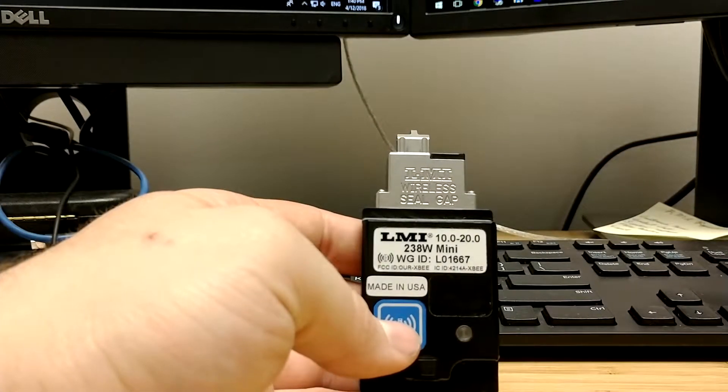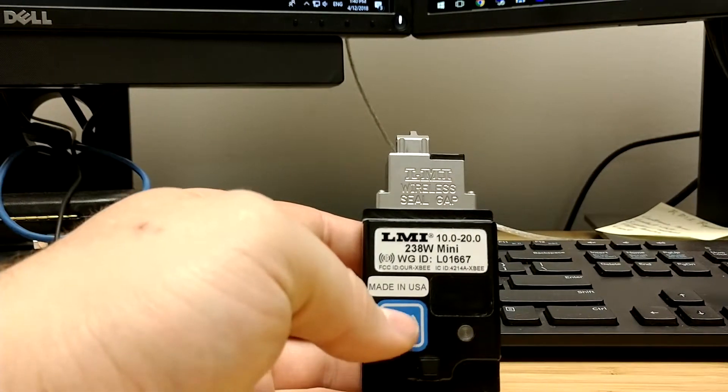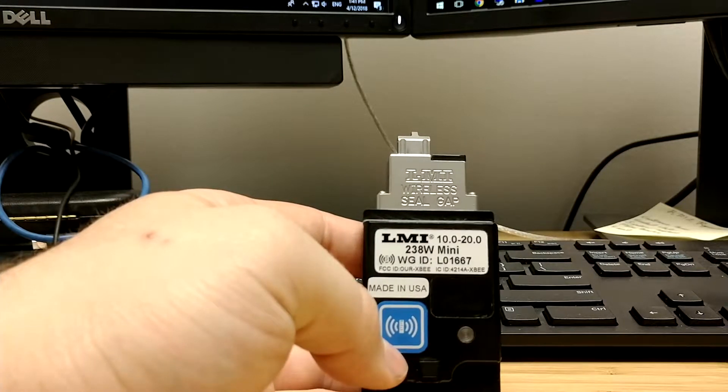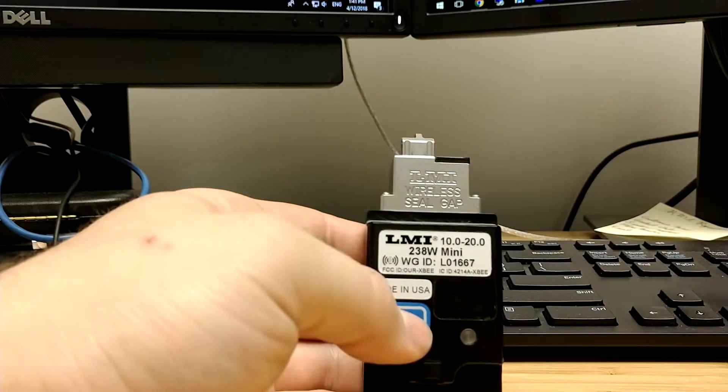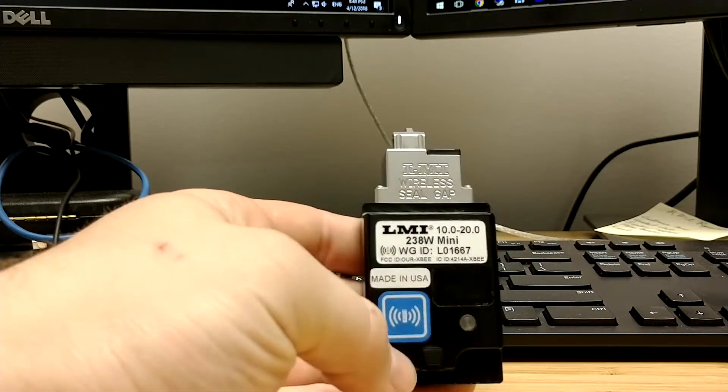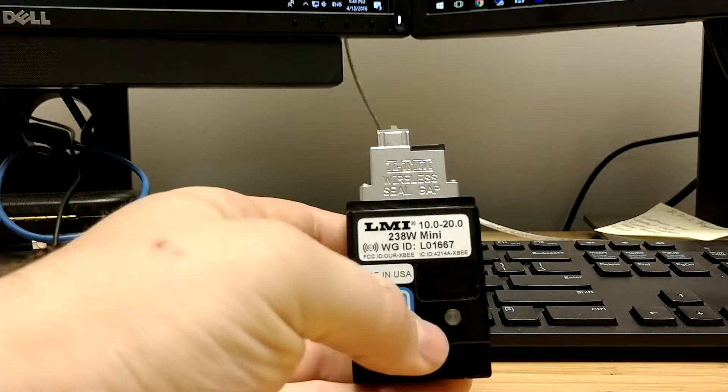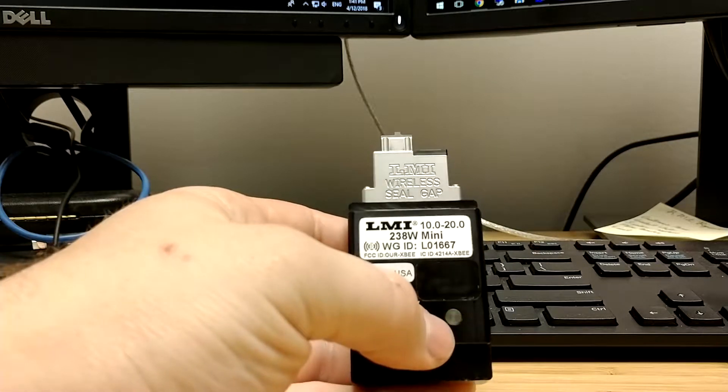Welcome to the association and calibration of the wireless seal gap gauges. To begin, open up wireless utility and press and release the blue button on top of the gauge to put the gauge in setup mode.